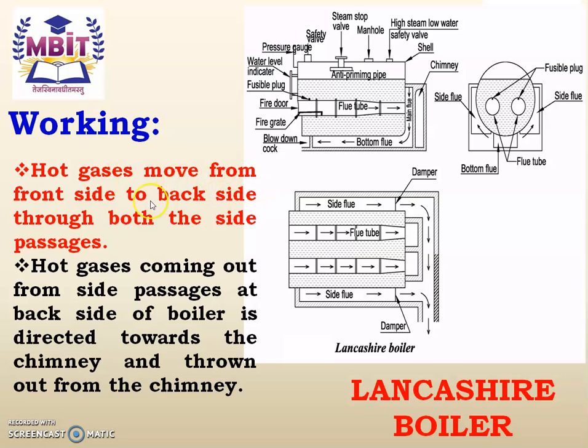Hot gases move from the front side to the back side through both the side passages. From the side flue, hot gases pass from the front side of the boiler to the back side. Hot gases coming out from the side passages at the back side are directed towards the chimney and thrown out into the atmosphere. A damper is provided before the chimney. If the hot gases are sufficiently hot, the damper is closed so that the hot gases remain inside the side passage and continue to heat the water and convert it into steam.